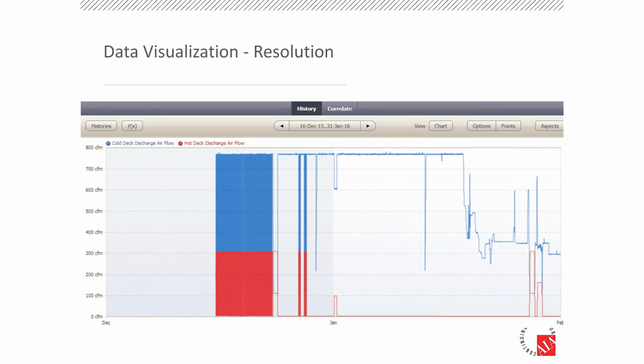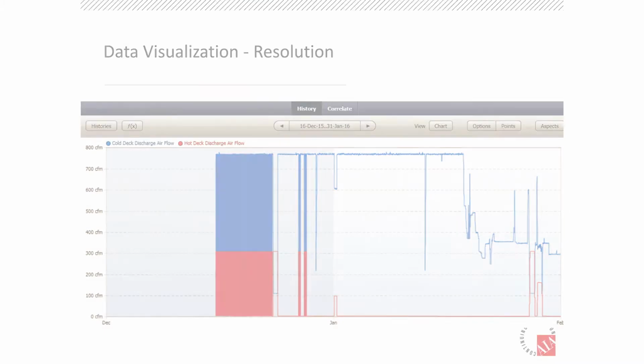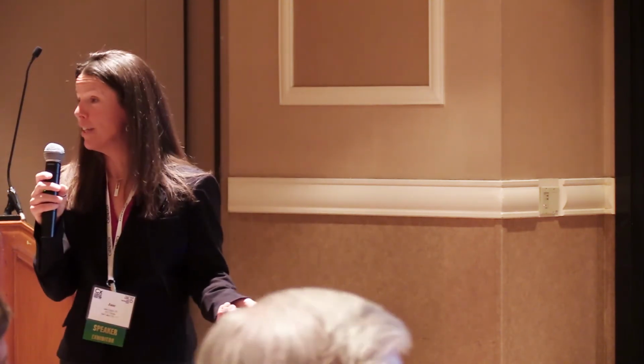So this is the big picture of the resolution that looking at this data allowed the construction team to come together and fix. Had this building not been commissioned, this is what would have been delivered to the owner: hot deck, cold deck, erratic behavior. Now they're operating down here with modulating flow to the laboratory spaces.